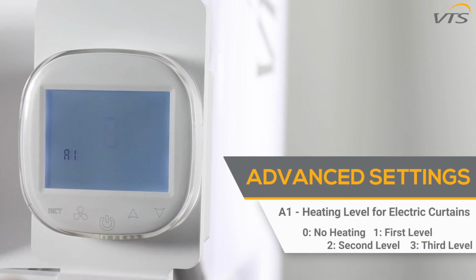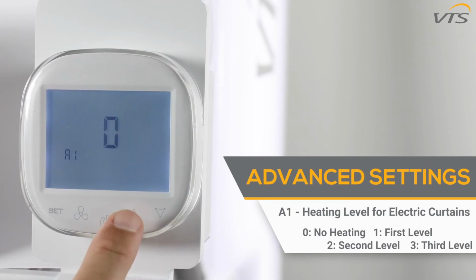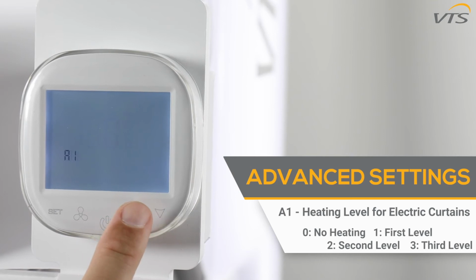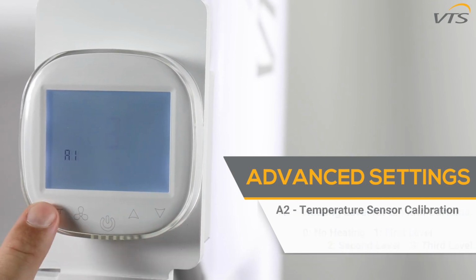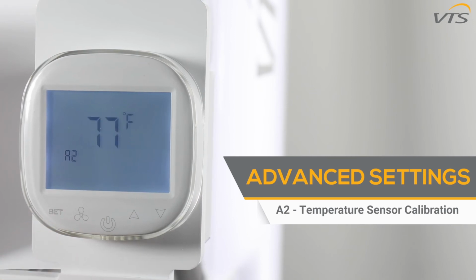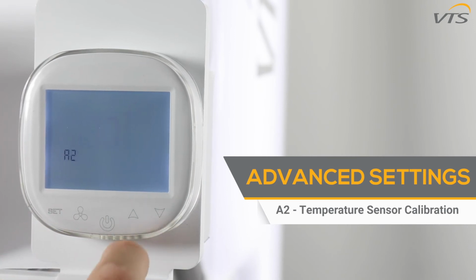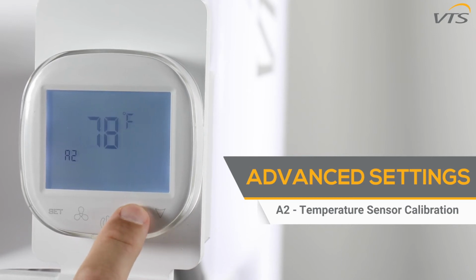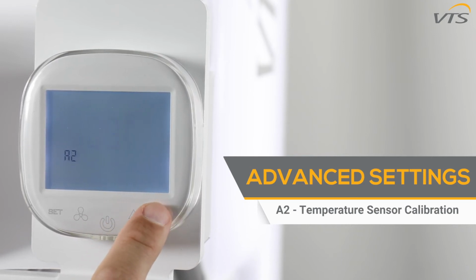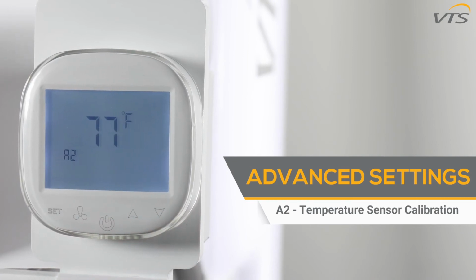The A1 function is to select the heating level settings for electric curtains. 0 is for no heating, 1, 2, and 3 are the first, second, and third heating levels. The A2 function controls temperature sensor calibration. If the actual room temperature differs from the one indicated by the controller, you can correct the sensor by using the up and down buttons, the correct amount, to make sure the temperatures align.